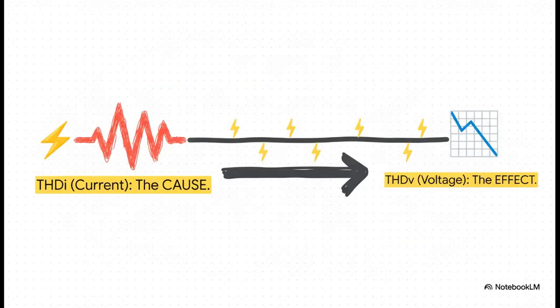We have to separate the cause from the effect. The cause is current distortion, or THDI. That's our devices drawing power in those weird, choppy pulses. As all that messy current flows through the grid's wires, it creates a distorted voltage drop. That gives us the effect, voltage distortion, or THDV. And that's the problem that everyone connected to that circuit ends up feeling.